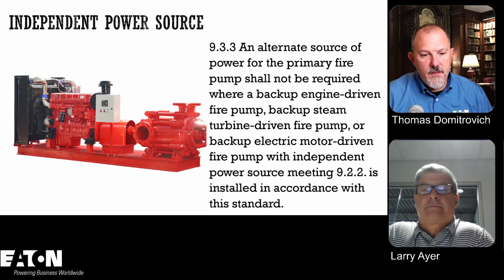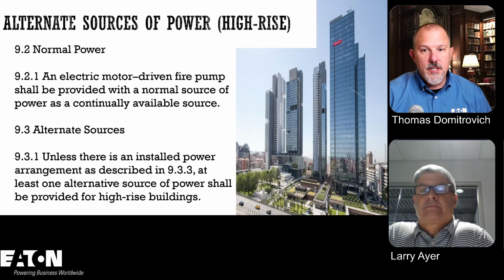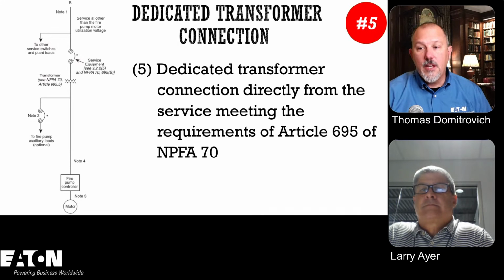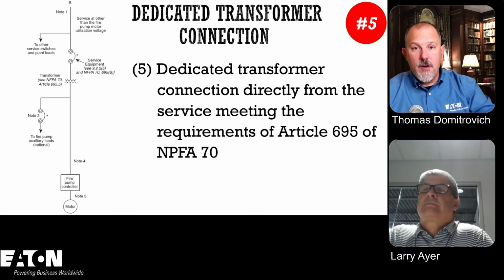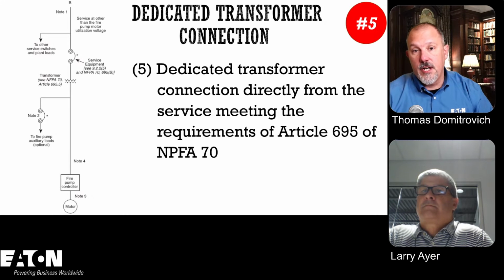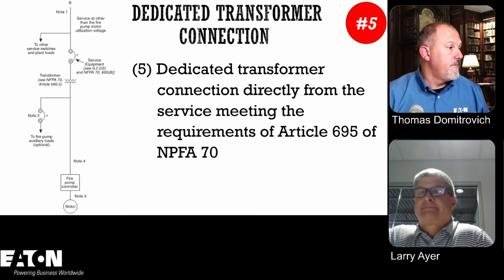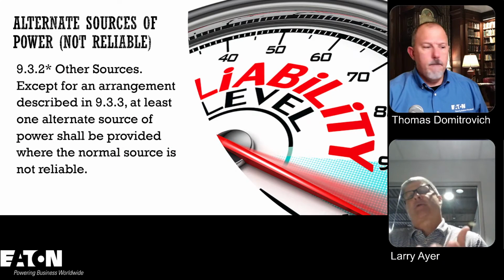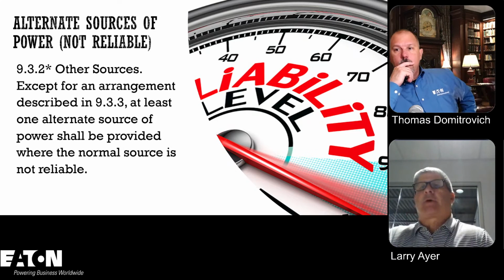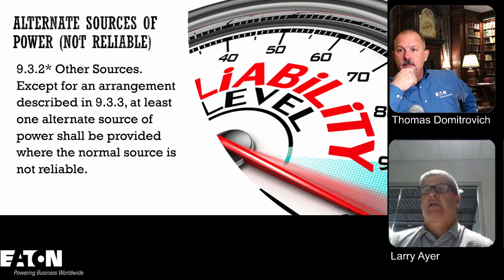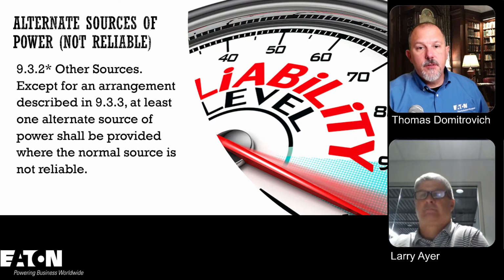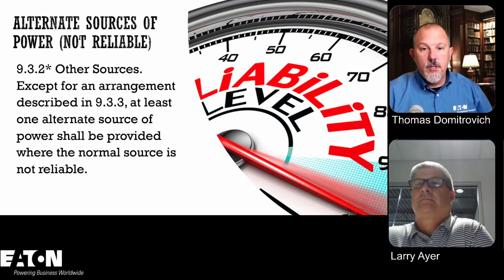Mohammed says, based on that picture in the previous slide, you're not allowed to have an overcurrent protective device on the secondary of the transformer if there is primary protection. So he's looking at this slide here. I think what your point was, Larry, is you don't need it if you have primary protection. We're saying you need the primary protection. Okay, that's a definite requirement. That's a requirement for transformer protection, period. But you're not allowed to have secondary protection, regardless of what it says in Chapter 4. Correct. Hopefully, Mohammed, you got that one. When you go to that fire pump controller, in all reality it's going to have some type of overcurrent protection in it. Excellent. All right. And then 9.3.2 says other sources, except for an arrangement described in 9.3.3, at least one alternate source. And we already talked about that.